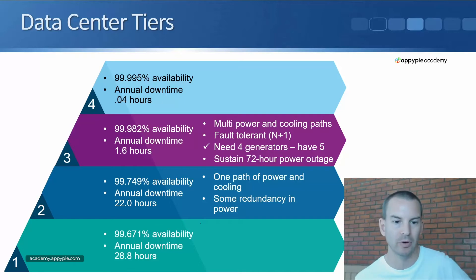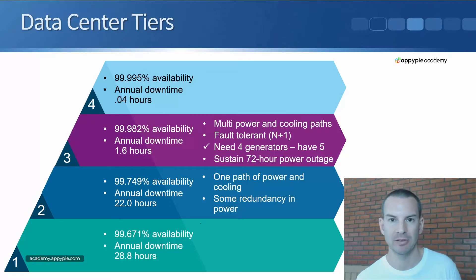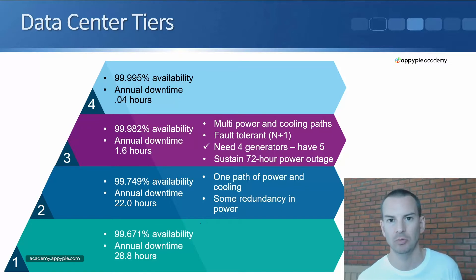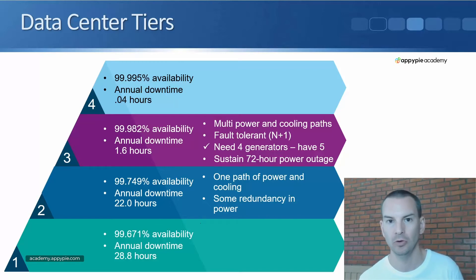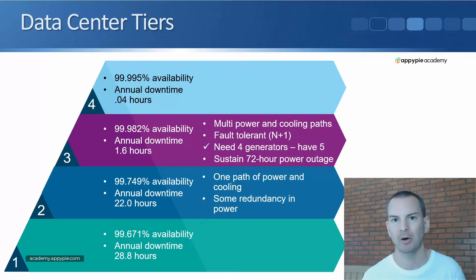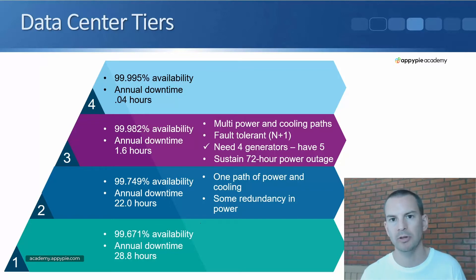Starting at the bottom layer, we've got a tier one, which is expected to have a 99.671% availability, equating to an annual downtime of 28.8 hours. With tier one, there are no requirements for redundancy. With a tier two data center, it needs to be more available, so an annual downtime of only 22 hours. It only requires one path of power and cooling — we don't need physically separate redundant paths — but we will expect to have some redundancy for some of the power components.